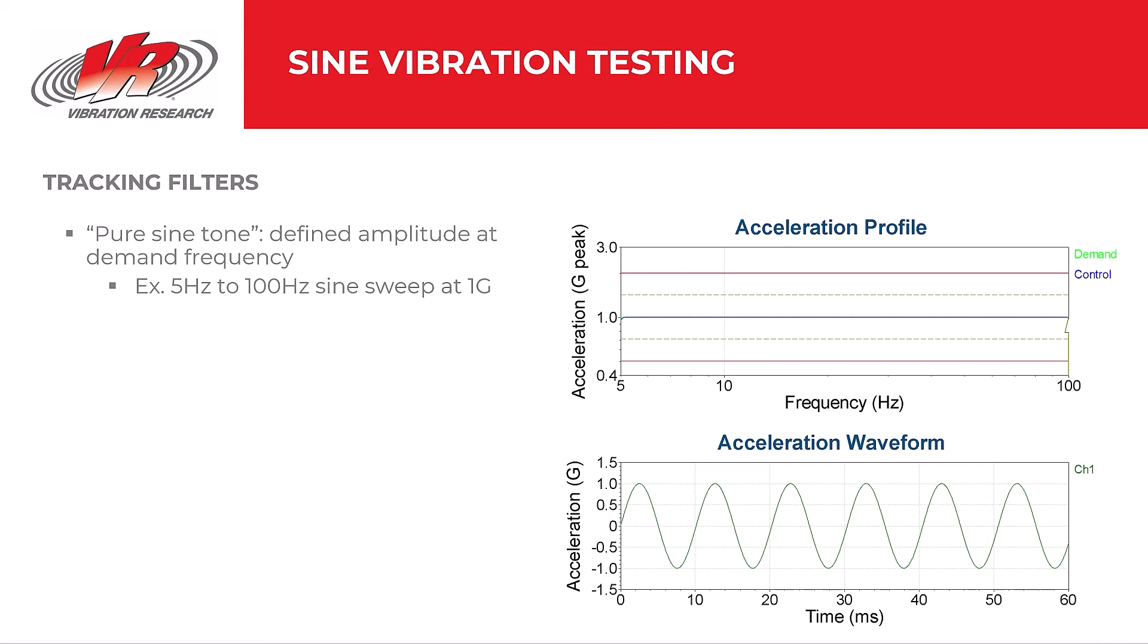Let's begin with sine vibration testing. Tracking filters is our primary focus when discussing filtering for sine vibration testing. To understand the importance of tracking filters, we need only to remind ourselves of the purpose of sine testing, which is to run a pure sine tone, a single frequency sine tone at a defined amplitude. Now, our test might sweep through a range of frequencies, but it runs one frequency at a time, and not simultaneously as it would for random vibration testing. For example, if we run a sine sweep from 5 Hz to 100 Hz at a 1 G acceleration, the system should control the test at 1 G as it sweeps through each frequency.